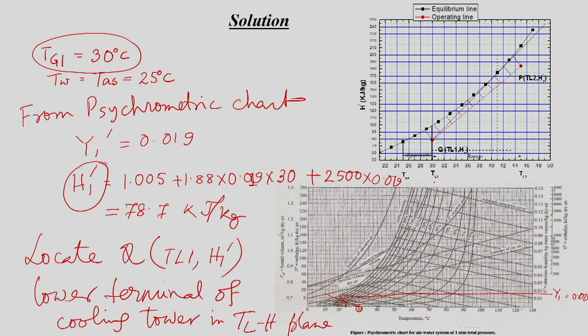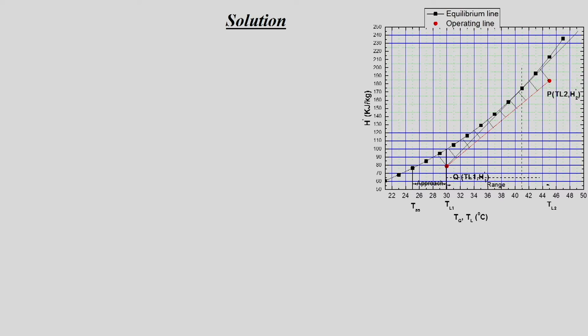In the TL-H plane, the lower terminal point has TL1 = 30°C and enthalpy 78.7 kJ/kg. This point is now identified. We then proceed to generate the equilibrium curve for the temperature range from 20°C to 47°C, within which the entire cooling tower operates.